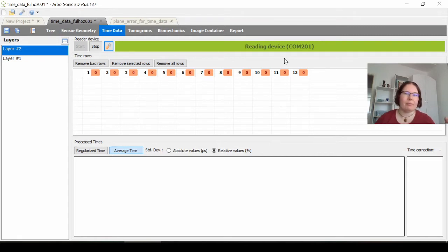You can grab the metal hammer and hit the sensors. Please remember to hit in the nail's direction at the head of the sensor. Don't hit anything else. Please don't hit the cables or the side, and try to have a loose wrist and try to hit very similarly. So keep your hit the same as much as you can. I will show you a simulation right now.